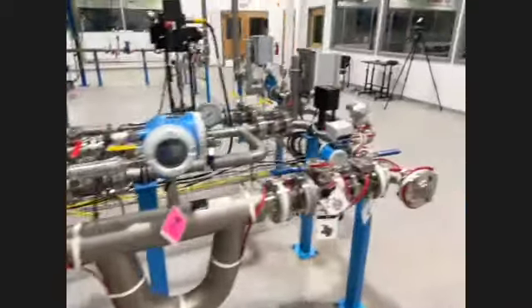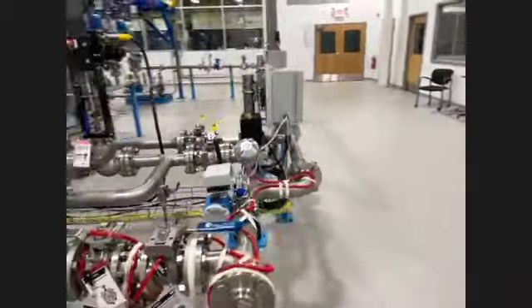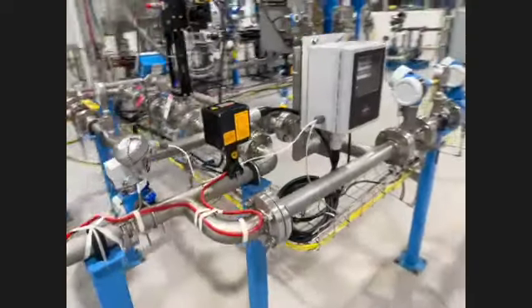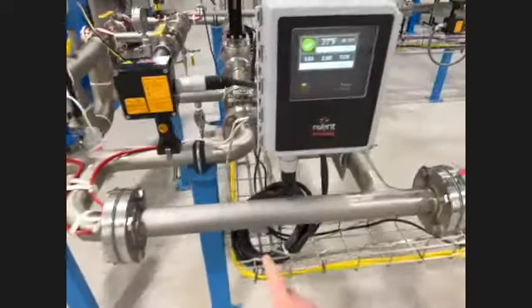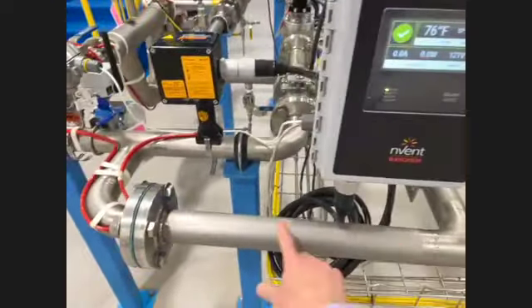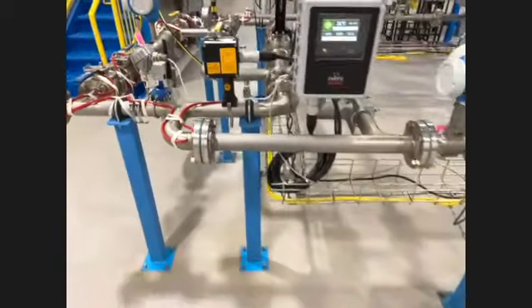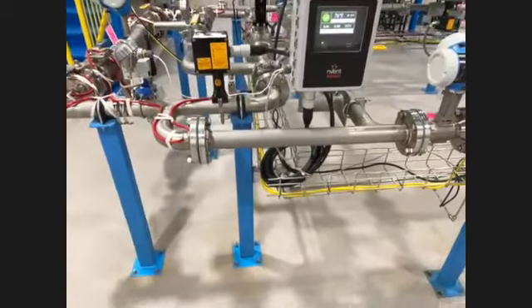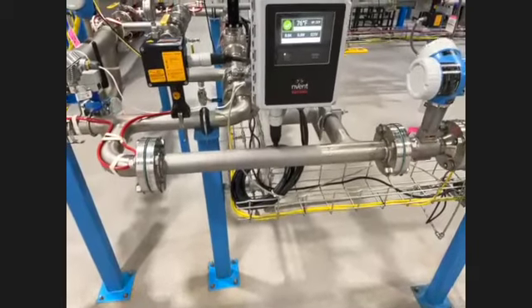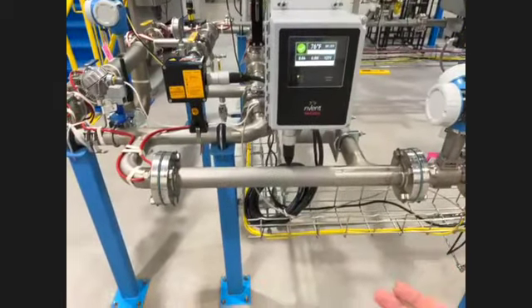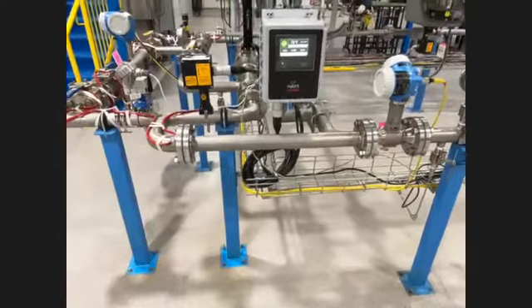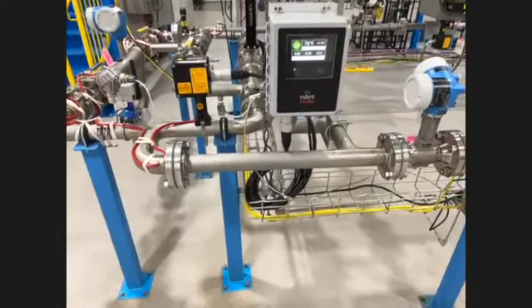So in summary, when we size heating cable, what we're doing is a heat loss calculation along a straight portion of pipe. For example, let's say we do a heat loss calculation and we're trying to maintain 6 degrees on that pipe when there's 1 inch thick mineral wool insulation, and that heat loss is 4.3 watts per foot, we'll say.